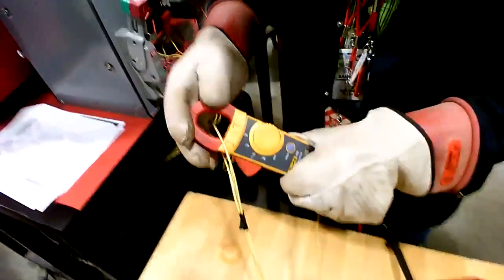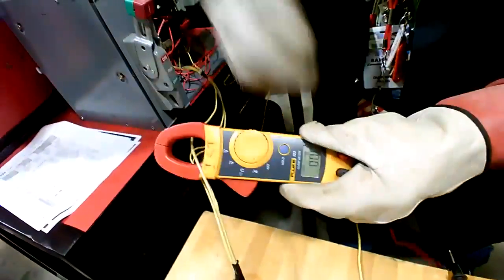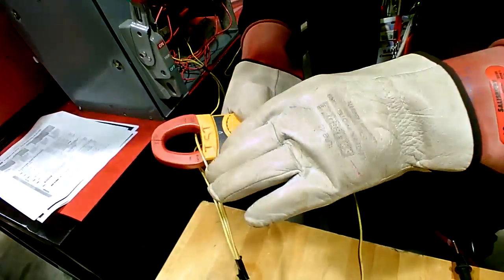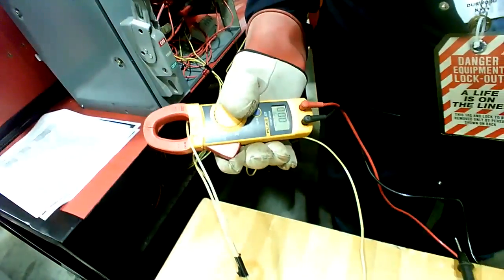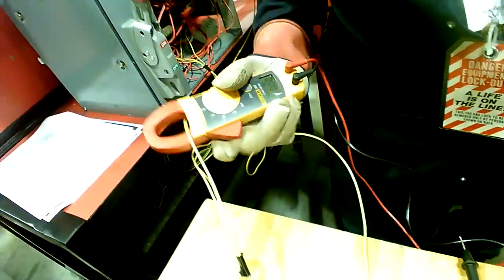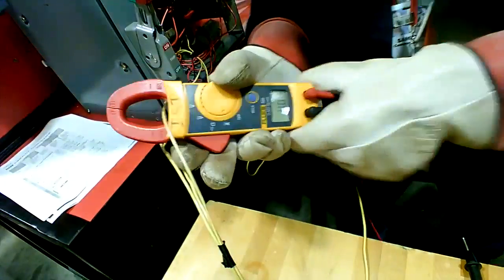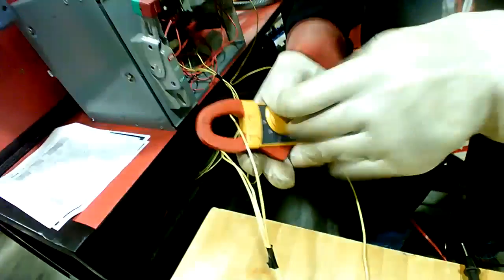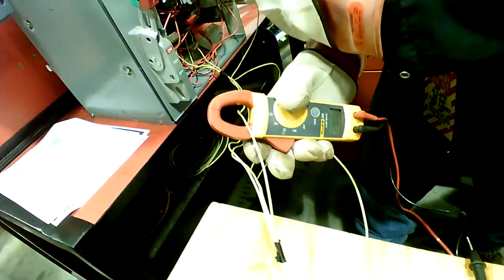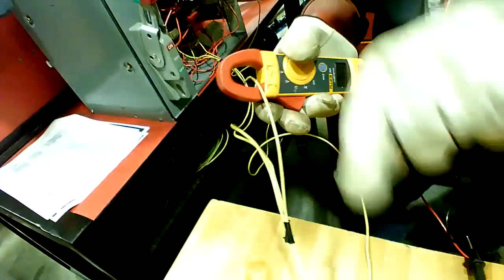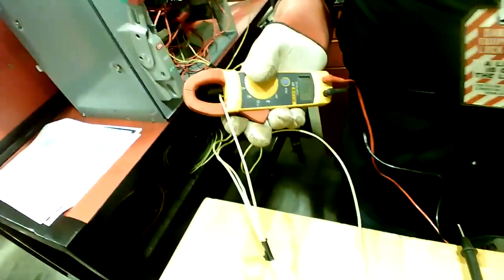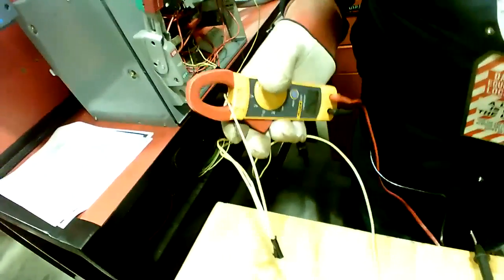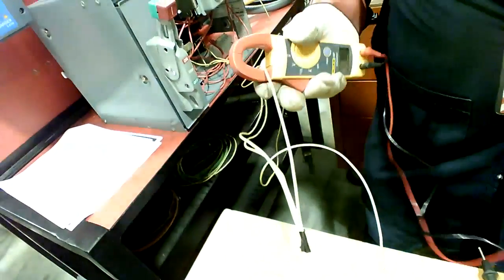But when you get out here and you're checking your amps per leg, and all of a sudden one leg shows up way less than the other, you have a phase imbalance on current. Now, let me ask you a question. Do you think you've got a problem up this way towards the bucket, or do you think you've got a problem that way towards the motor? Towards the motor.